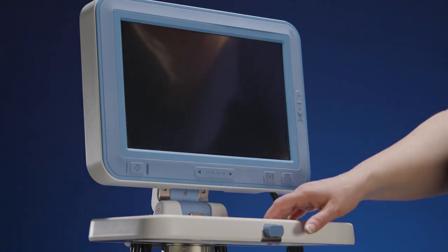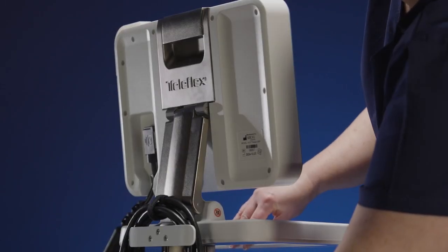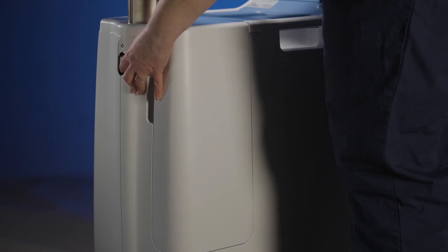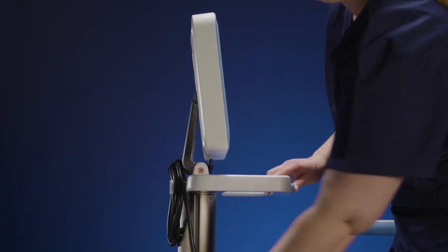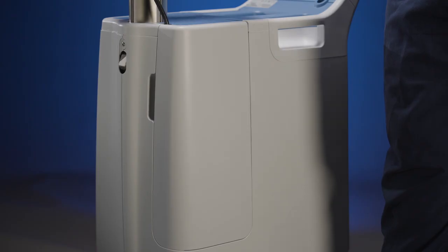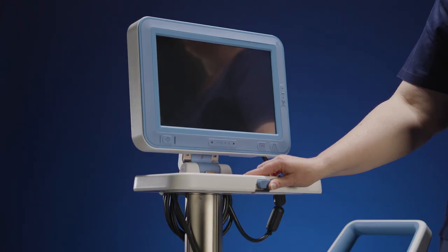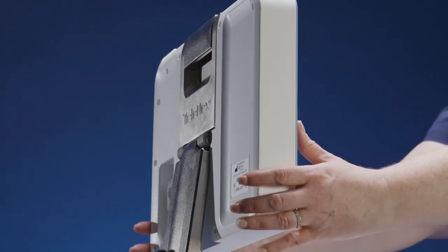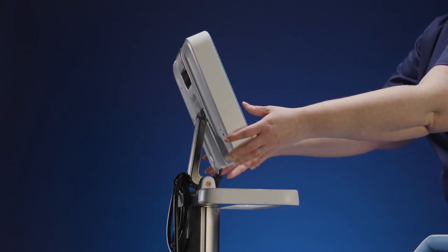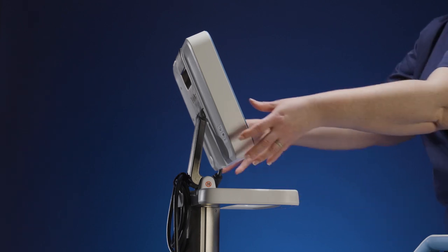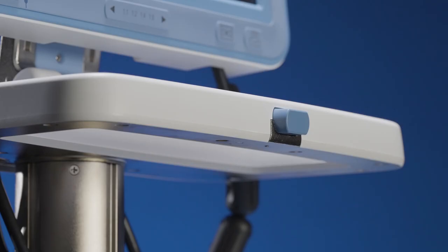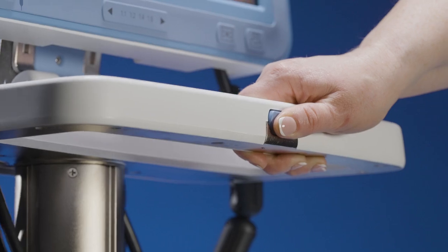The control display module is mounted on a bracket and can be rotated 360 degrees in either direction by pressing the button on the back of the pneumatic module. It can be locked in quarter turns. The display can be raised or tilted to allow for better visibility. To raise and lower the control module, press the blue button on the control module handle.